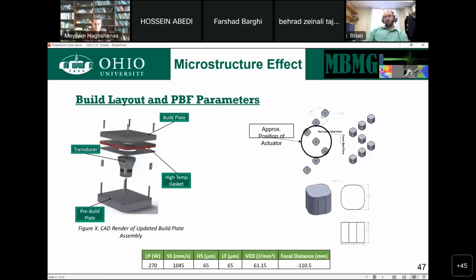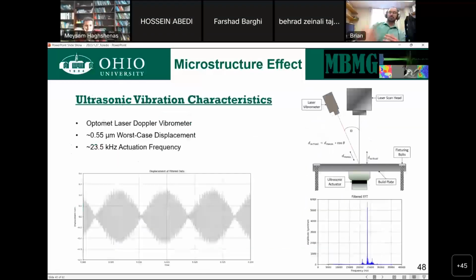We did some studies across different locations on the build plate, the circle representing the transducer. So we have samples directly on top of the transducer and those next to the transducer to understand, if we're clamping this into a traditional system, how is that affecting the ultrasound at different locations? And we actually used the laser I told you before in order to see what kind of energy we were supplying. In this case, we're applying about 0.55 micrometers at the center with a 23.5 kilohertz actuation frequency.